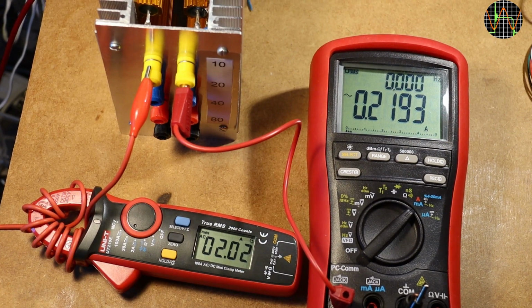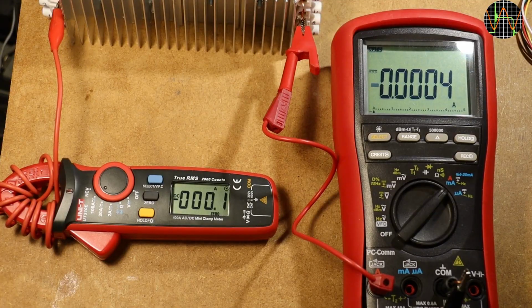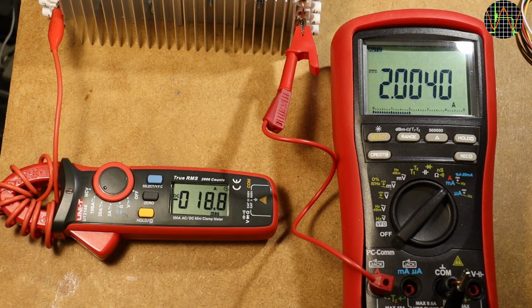And here's the same for the AC 20 amp range. After both AC and DC measurements are complete and in a spreadsheet, I followed the same procedure shown earlier to first remove the wrong 60 amp correction factor, then calculate the new correction factor for each value, pick a suitable average correction factor and apply that instead. Now for currents beyond 20 amps, I considered using thinner wire to add more turns on the clamp, maybe 50 would be feasible, but a lot of work.